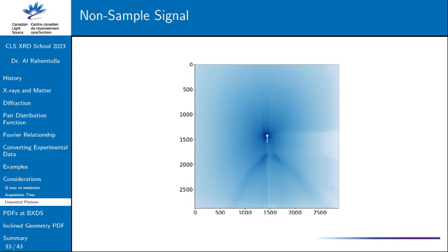So while this is very little, it can all contribute. The nice thing is that the solution is we just need to collect this data and have it in our back pocket so we can subtract it from our data. If you have very dense samples that are very attenuating, you might want to have more subtractive samples because you might have to play with scaling of how things need to be corrected, since your sample is also going to be blocking some air scattering.